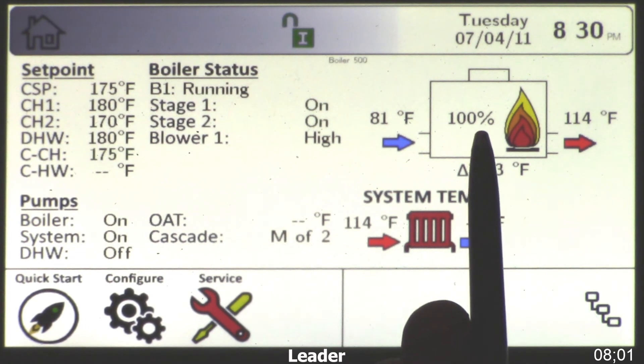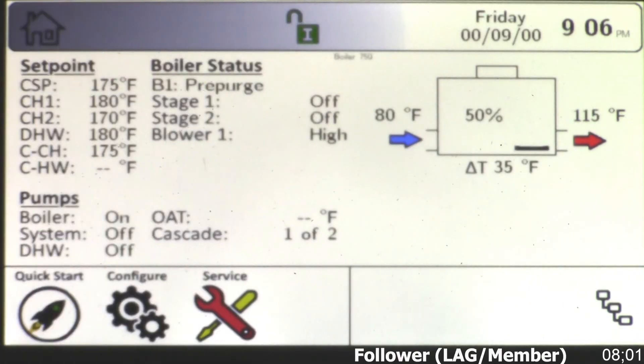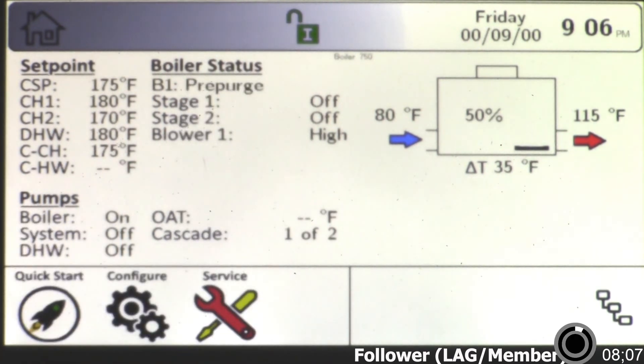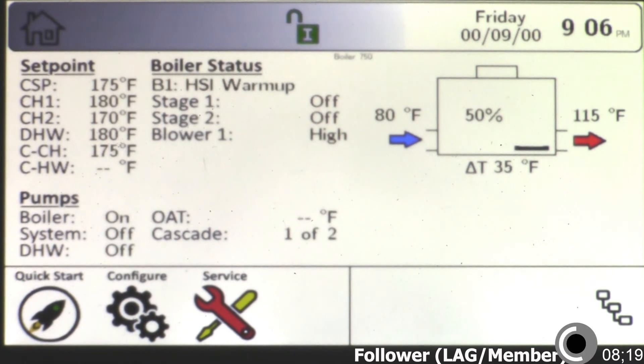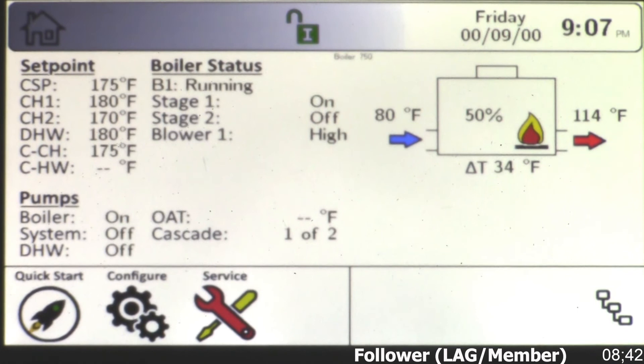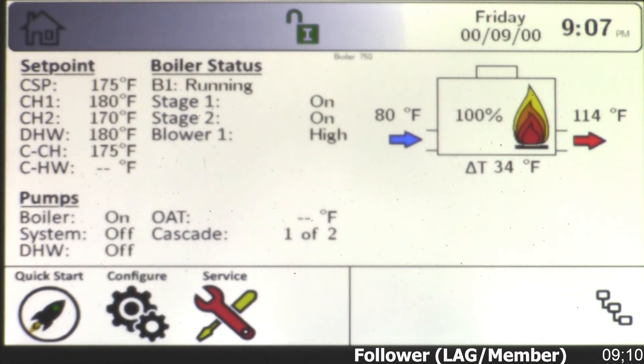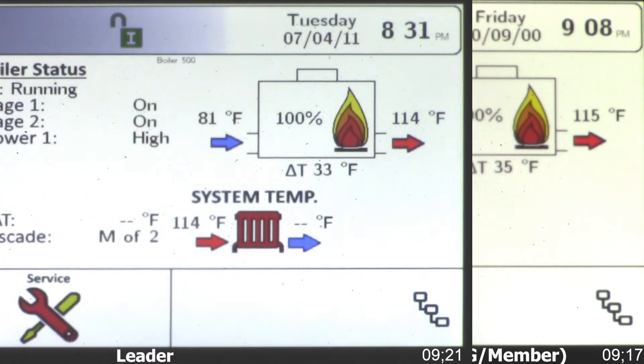Now at 100 percent of fire, we'll start to enable our first lag boiler. Over here on our first lag — one of two — we're now in pre-purge, then HSI warm-up. It's going to go through the same sequence and light. Now we're running on our first member boiler at 100 percent. Both boilers in this example are running at 100 percent. Now I want to simulate what happens if you lose the leader — I will shut off this leader and focus on that member boiler.